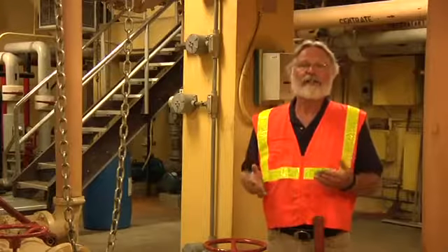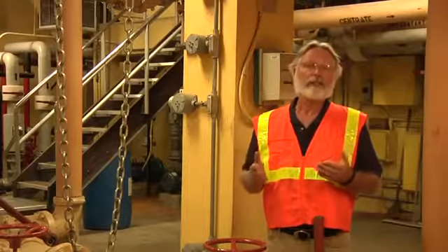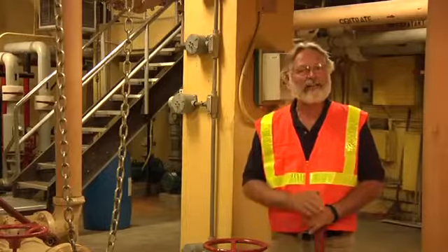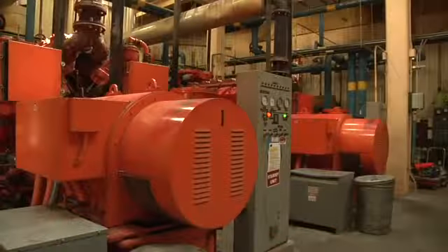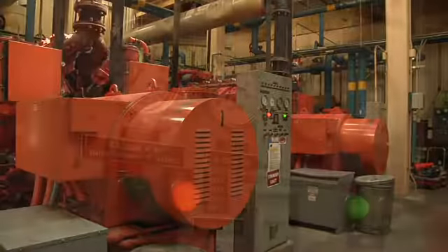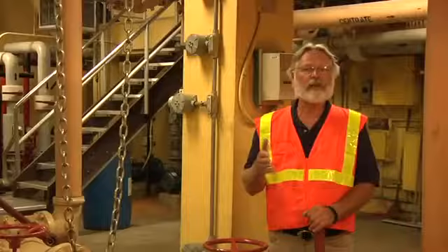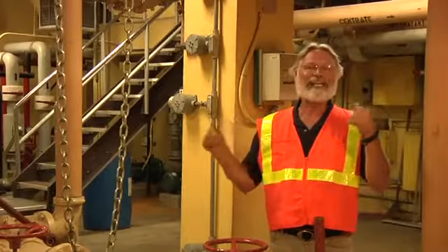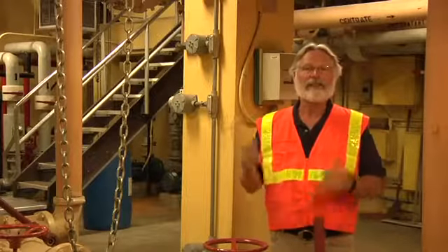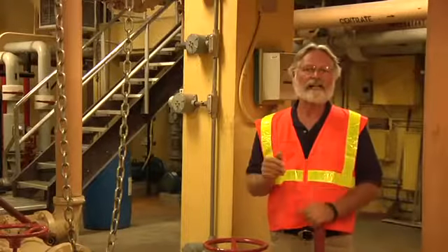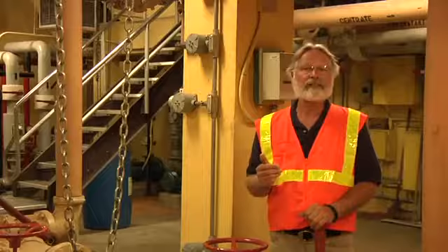When we're finished, the sludge is turned into a useful product. But during that process, we also generate some methane. That methane gas we can use to run generators, and those generators power part of our wastewater treatment plant. They also generate waste heat, which we use to heat up the digestion process. So it's a nice circle. We use a whole lot of the energy that's stored inside that sludge to make our process cheaper to operate.